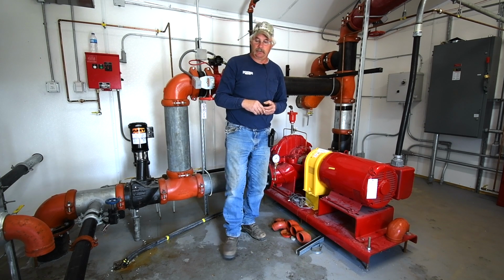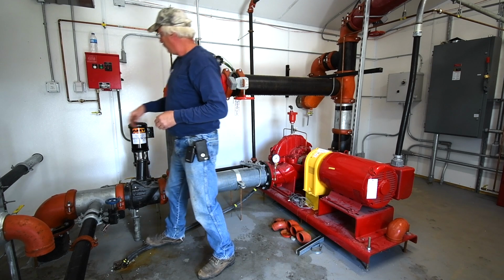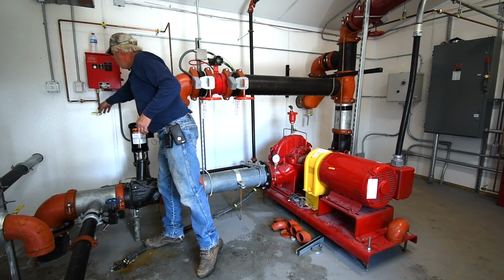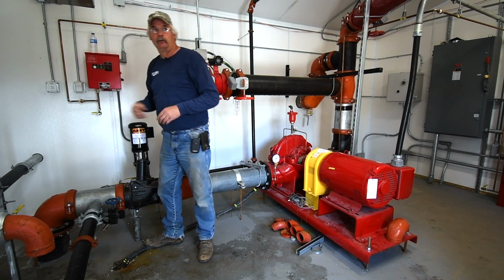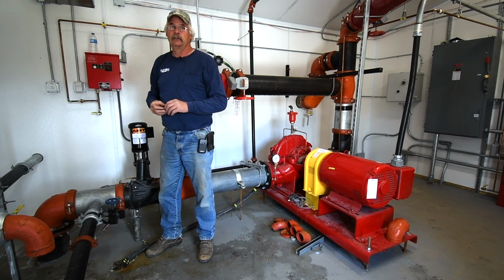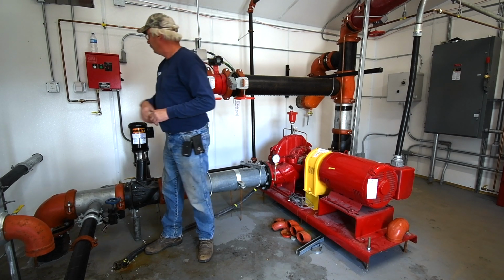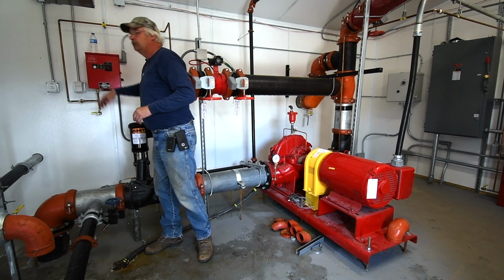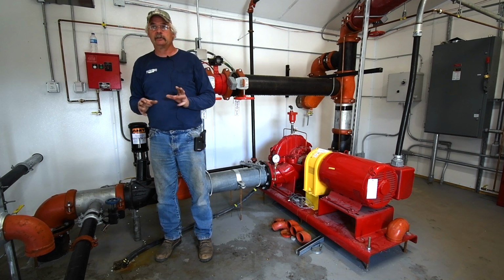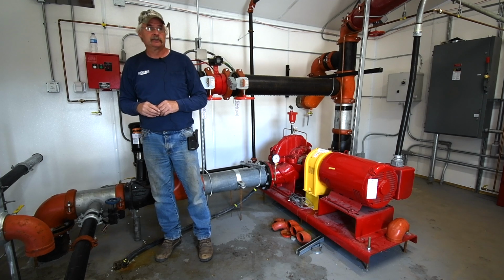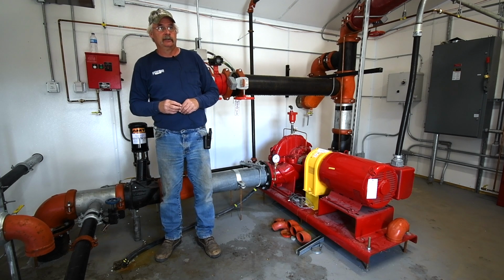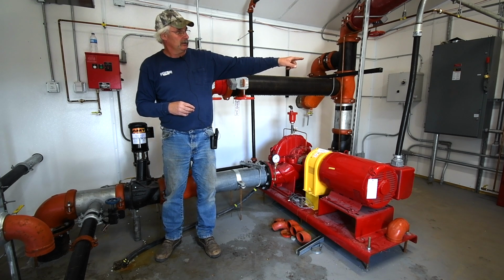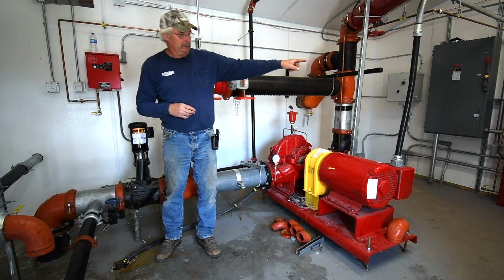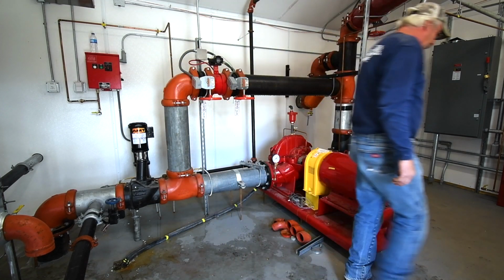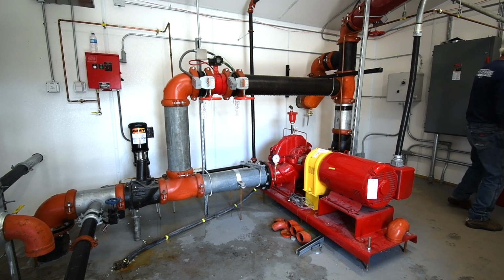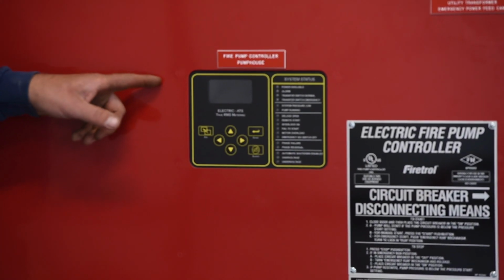Also, the sensing lines will be cleaned out. There are 1/2-inch ball valves below, so we'll flush the lines. The lines are all brass and copper, so that nothing corrodes or builds up. The cabinets themselves are preset pressures. There's no reason to adjust any pressures. The fire pump controller has a digital readout on the front door, right in the front right there, that will show you all the different functions of your fire pump.